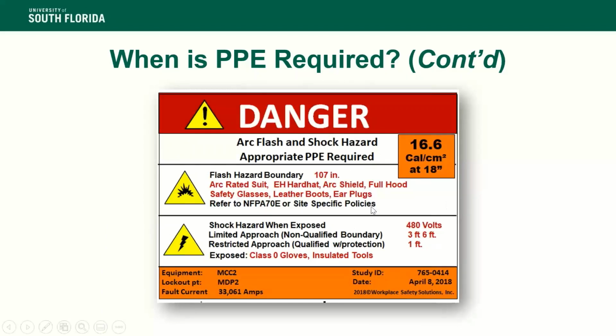This is another one that was just covered. During some of the consultation visits I go out on, I pay close attention to see if I can find this tag on the circuit breaker panels. I've seen this out there in the workforce or at workshops I've visited. As Keith alluded to, this is a hazard boundary where the qualified technician is given the distance for that boundary, and then has an arc rated suit.